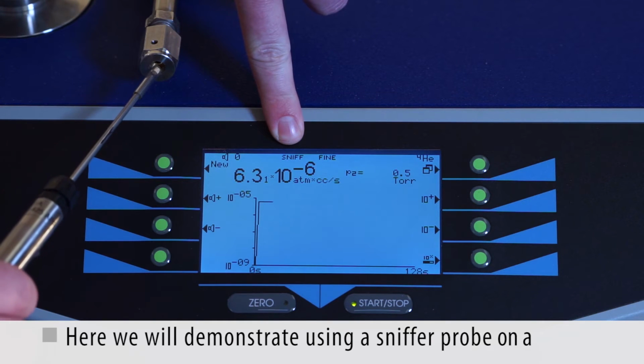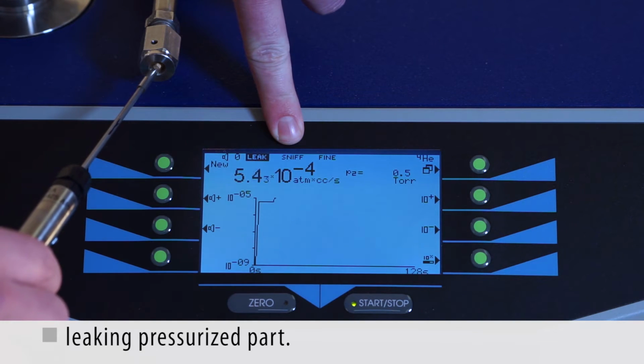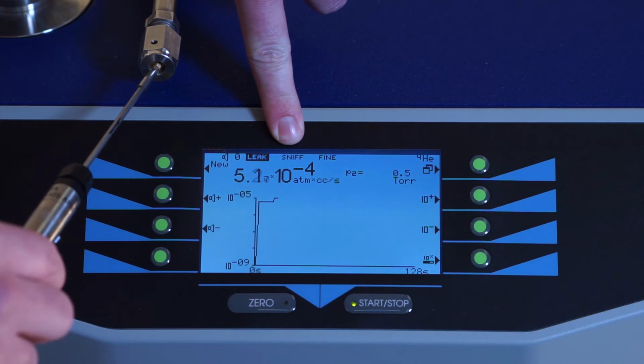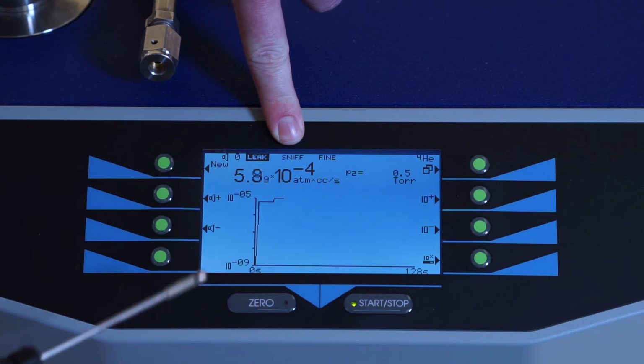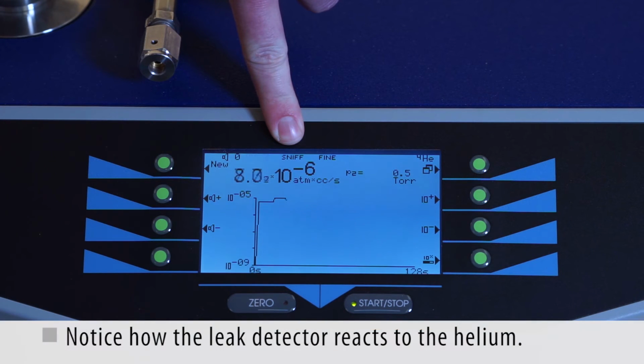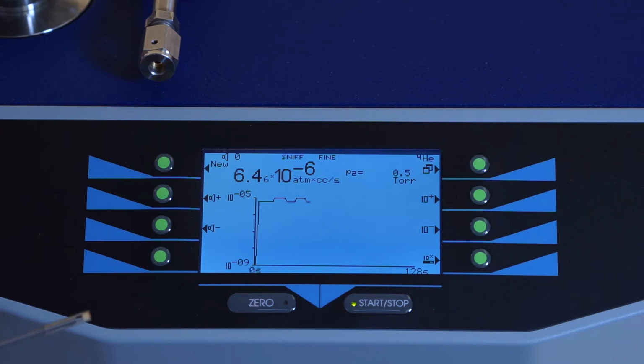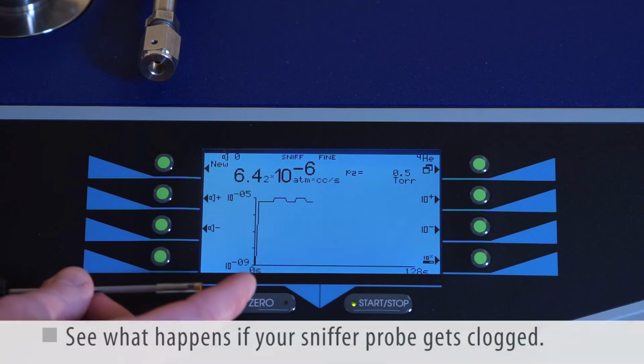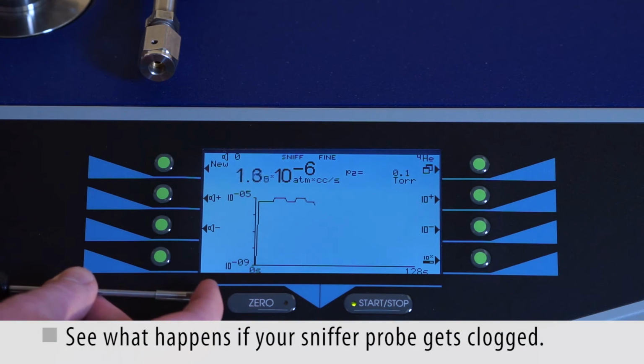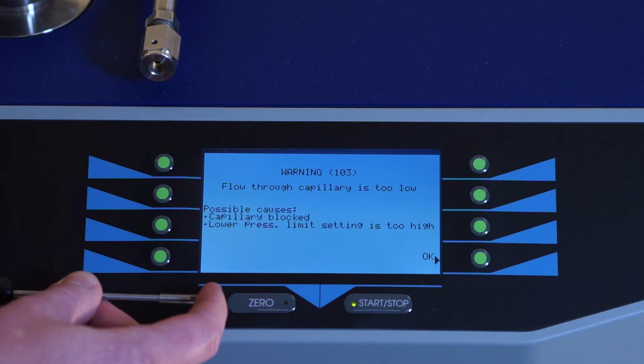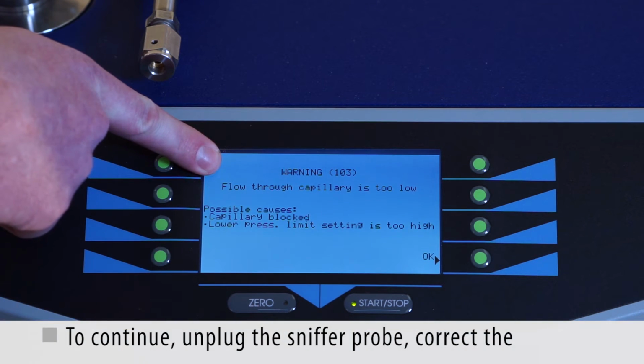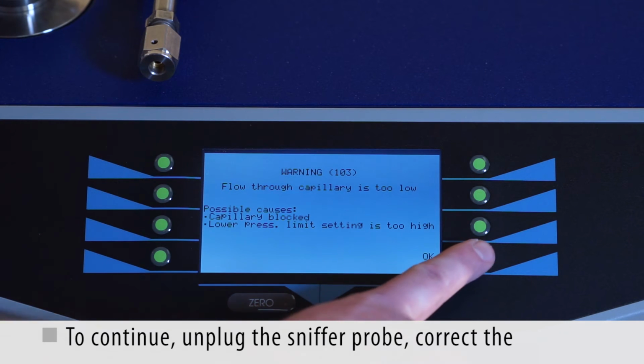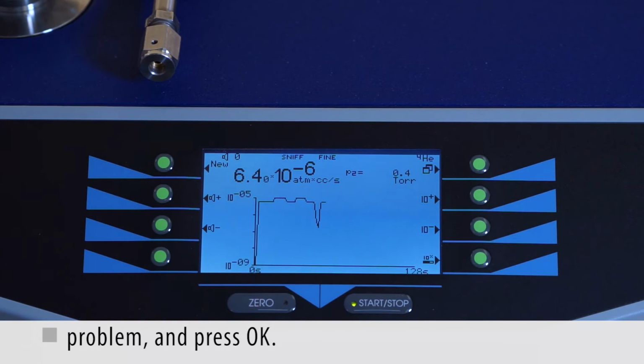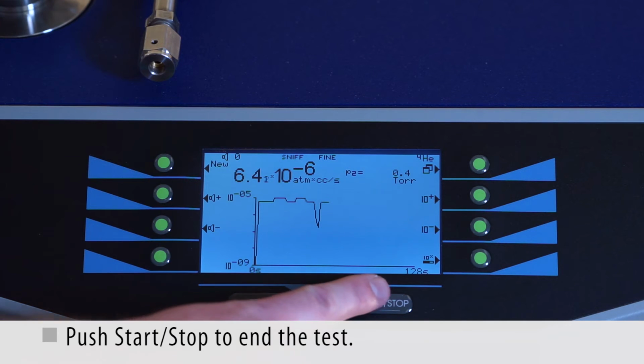Here, we will demonstrate using a sniffer probe on a leaking pressurized part. Notice how quickly the leak detector reacts to the helium signal. Now, see what happens if your sniffer probe gets clogged. To continue, unplug the sniffer probe, correct the problem, and press OK. Push Start/Stop to end the test.